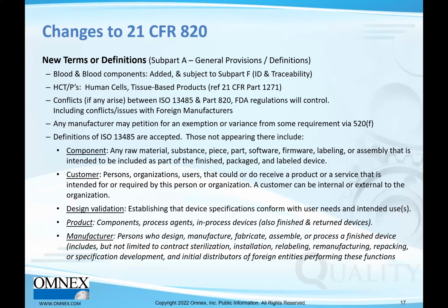Component. There is not a component definition in 13485. A component is any raw material, substance, piece, part, software, firmware, labeling, or assemblies that are intended to be included as part of the finished, packaged, and labeled device. Customer is not defined in 13485. That is persons, organizations, users that could or do receive a product or service that is intended for or required by the person or organization. A customer can be internal or external to the organization. Keep that in mind for inspections or audits, because internal customers are as important as external customers.